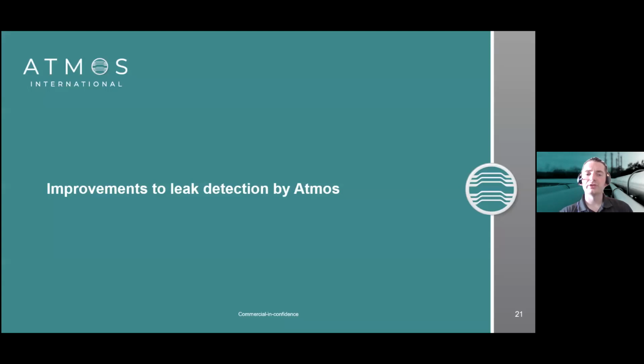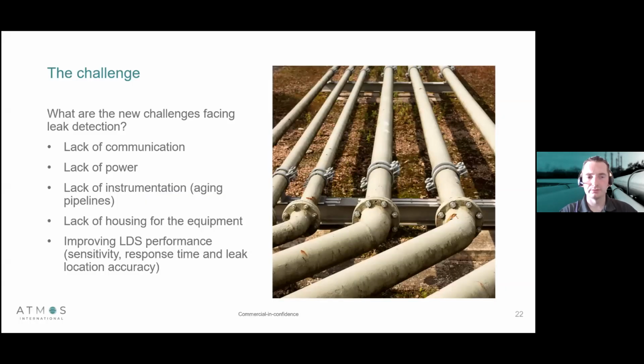So what improvements to leak detection have been made by Atmos? Well, as I said, there's lots of challenges still facing leak detection. As environmental policies change, as the API standards change, we're starting to see that a lot of pipelines, especially aging pipelines, now require leak detection. But we start coming up against challenges. When these pipelines were constructed, leak detection might not have been thought about. So we often face challenges like lack of communication, lack of power, and lack of instrumentation, and we even have lack of housing for the equipment in the locations we need.